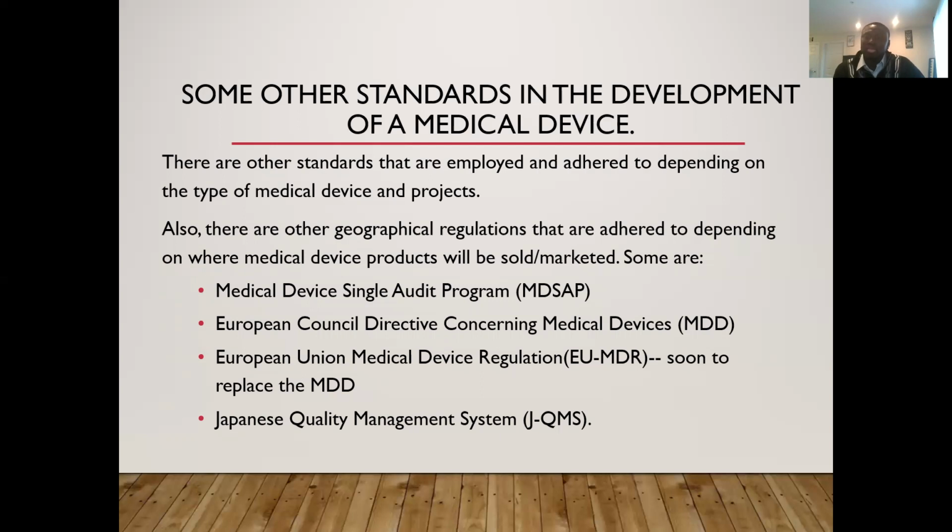And then we have the MDD, which is the European Council Directive concerning medical devices. If you want your product to be sold not just in the US but also in Europe, you have to be compliant with the MDD, the Medical Device Directive. And then also the EU MDR, the European Union Medical Device Regulation, which is going to replace the MDD very soon.